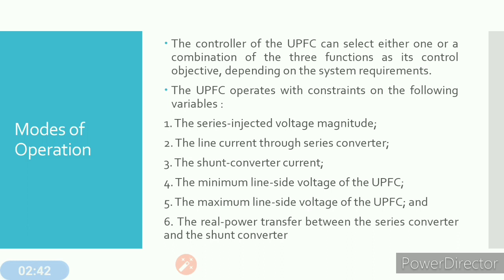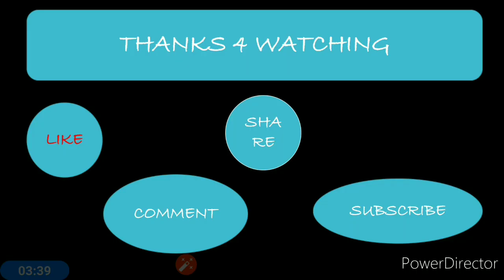The control of the UPFC can select either one or a combination of three functions as its control objective, depending upon the system requirement. It can work as one function, as a combination of one and two functions, or as a combination of all three functions simultaneously. There are six constraints controlled by the UPFC: the series injected voltage magnitude, the line current through the series converter, the shunt converter current, the minimum line side voltage of UPFC, the maximum line side voltage of UPFC, and the real power transfer between the series converter and the shunt converter.